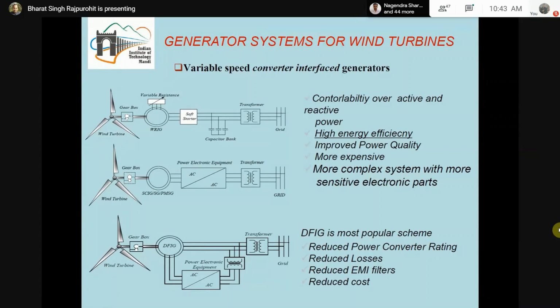Now you can also see that the stator is directly connected to the grid. So it means the power quality is also better as compared to the middle scheme, where the complete power is processed by the power electronic converters. In this case, the power is mostly fed directly to the grid, and some power is taken from the rotor side, processed, and fed back to the grid.